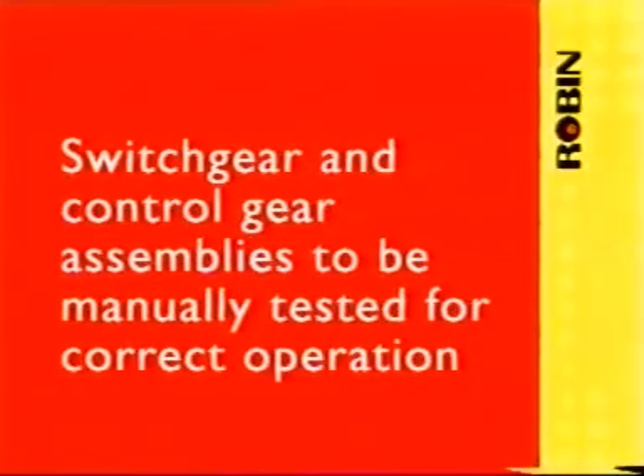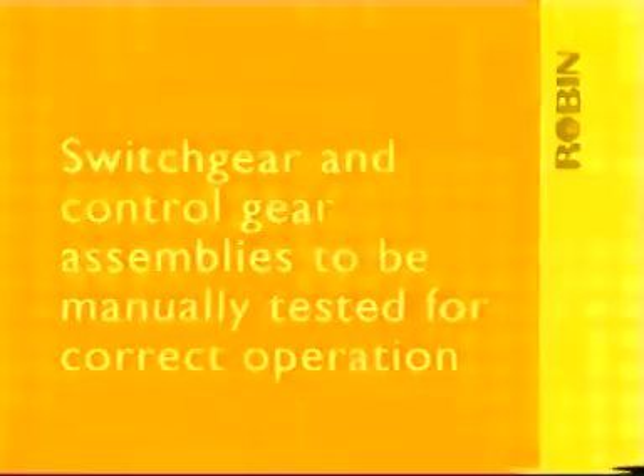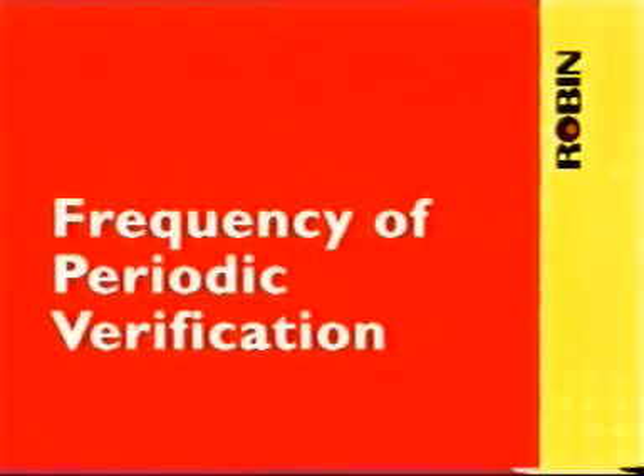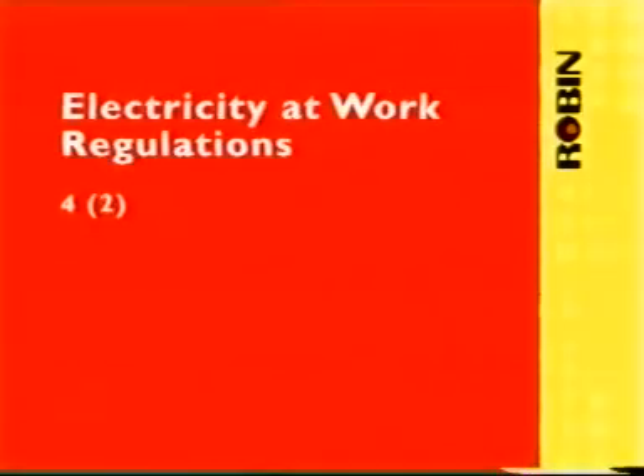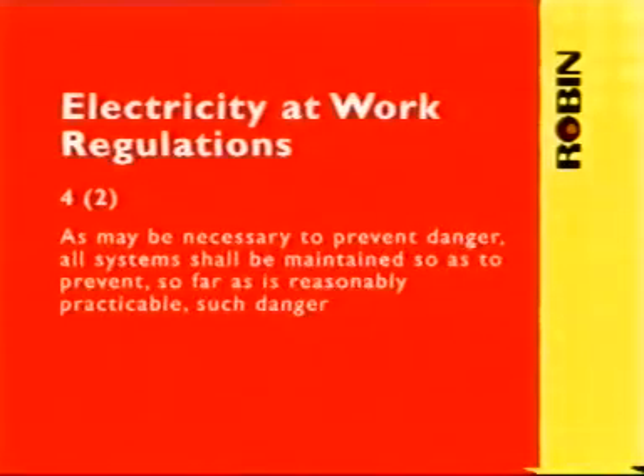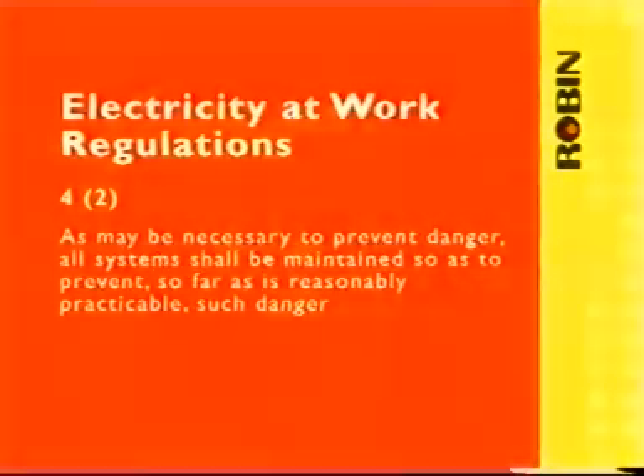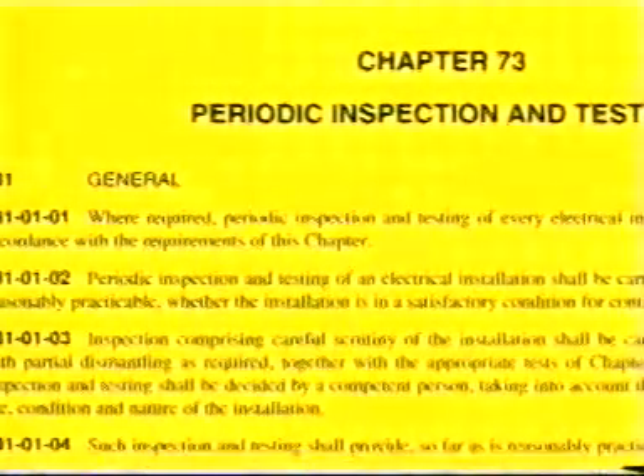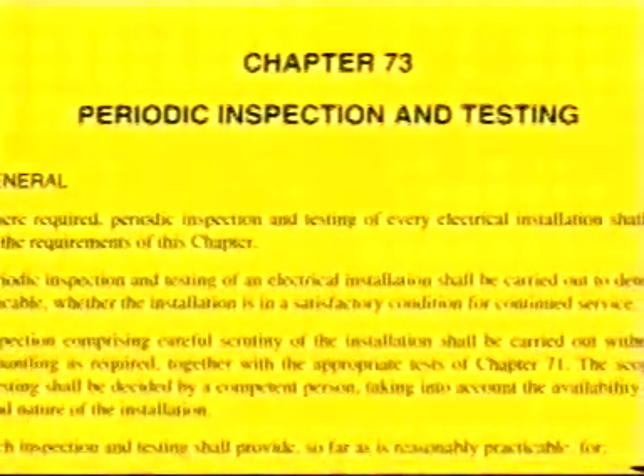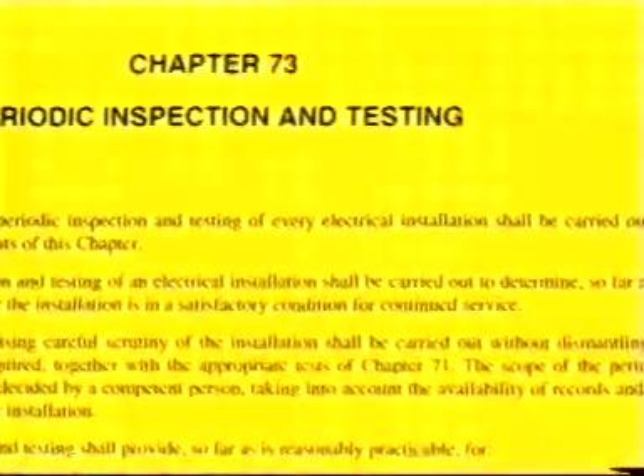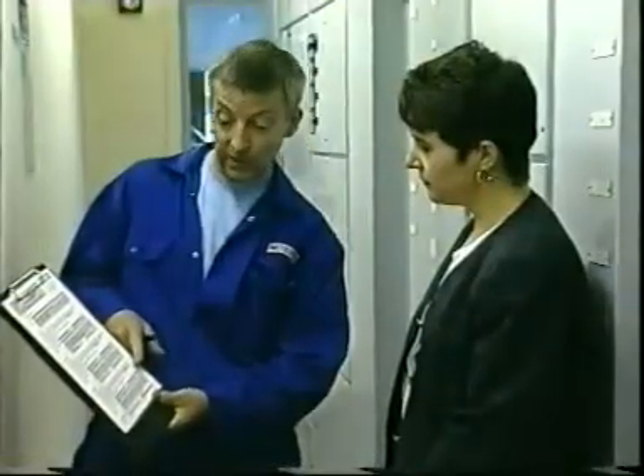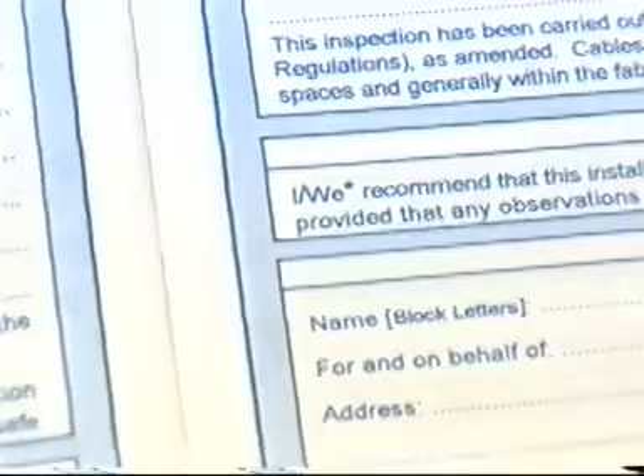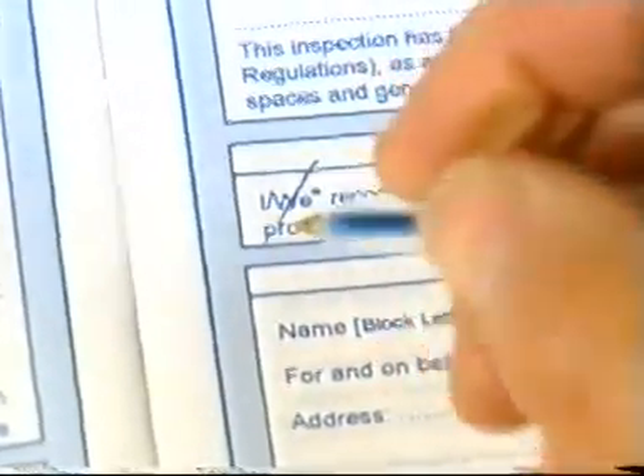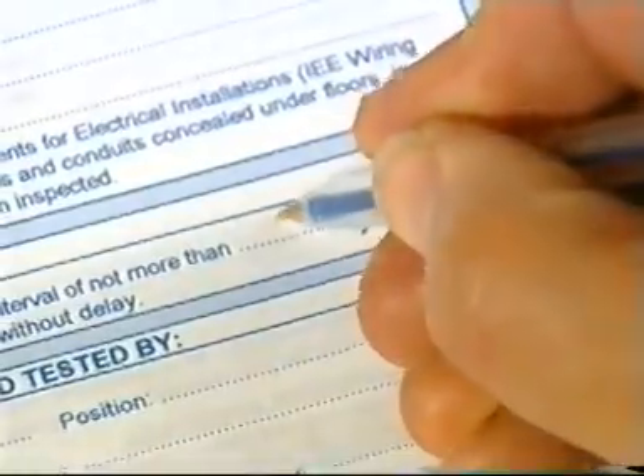Switchgear and control gear assemblies must be subjected to a functional test to confirm their ongoing acceptance for their intended purpose. Regulation 4.2 of the Electricity at Work regulations requires electrical systems to be maintained. Chapter 73 in BS7671 requires all electrical installations to be periodically inspected and tested. The installation user should be informed of the need for periodic testing with the next recommended inspection date recorded on the electrical installation certificate or periodic inspection report as appropriate.